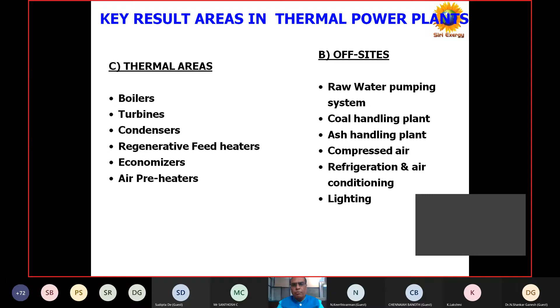In addition to that, the exit flue gas temperature. Most of the power plants are designed for around 142 exit flue gas temperature, but many times the exit flue gas temperature goes as high as 165 degrees centigrade. That means for every 21 degrees there is 1% loss. Those things we will quantify and tell, and we can fine tune the boiler to improve the efficiency. Then in addition to that, there is some more equipment in the plant.